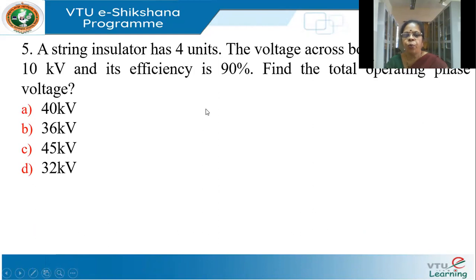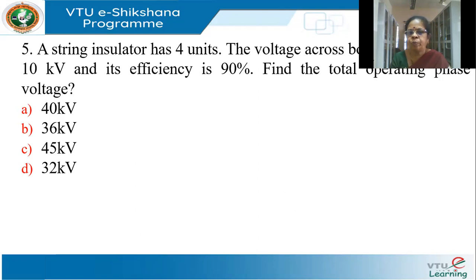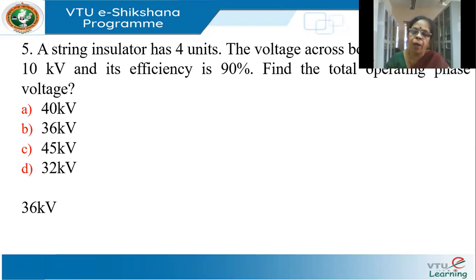A string insulator has four units. The voltage across the bottom-most unit is 10 KV and its string efficiency is 90%. Find the total voltage. String efficiency equals total voltage divided by N times the voltage across the bottom-most disk. So: 0.9 = V / (4 × 10), giving a total voltage of 36 KV. Multiplying 36 KV by root 3 gives the line-to-line voltage, but since that option is not given, the answer is 36 KV.